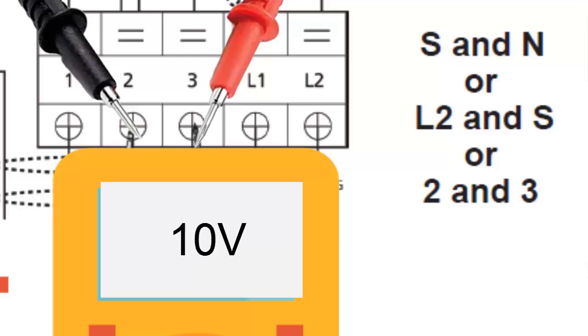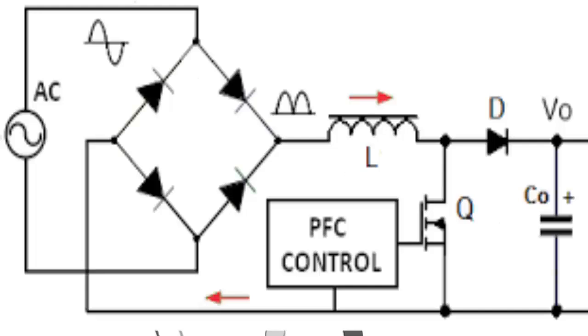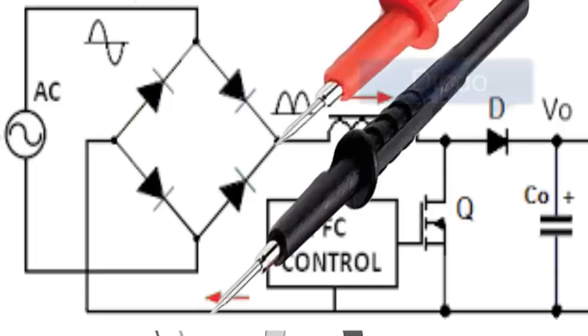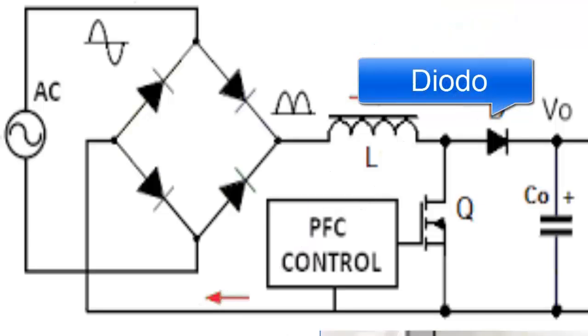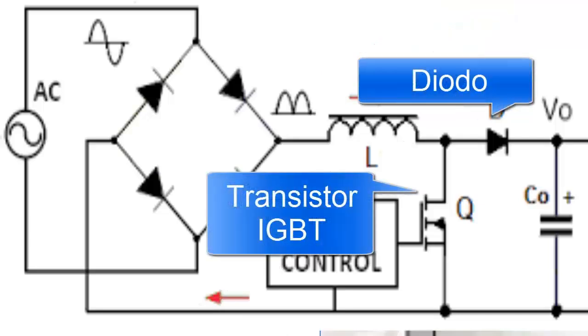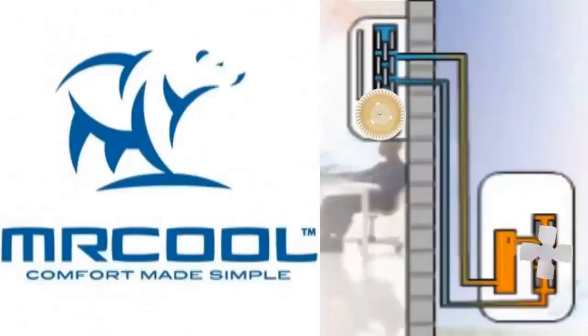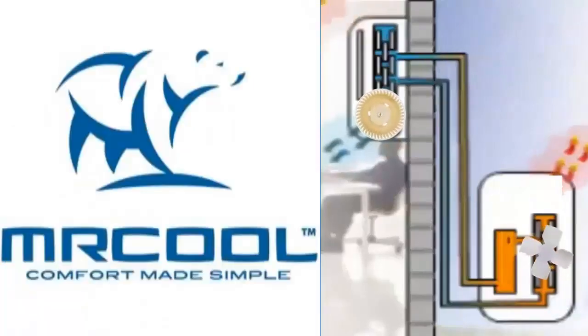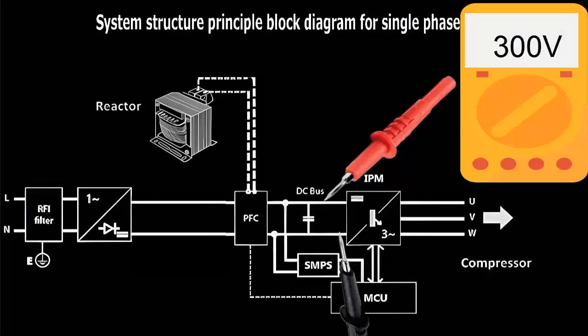9. In case of problems, it is recommended to check the PFC circuit located in the outdoor unit. Test the voltage at the output of the rectifier bridge, and check the fast recovery diode and IGBT transistor for faults, short circuits, or damage. 10. If no apparent damage is found, measure the DC voltage supplied to the Intelligent Power Module, IPM, to identify any issues.